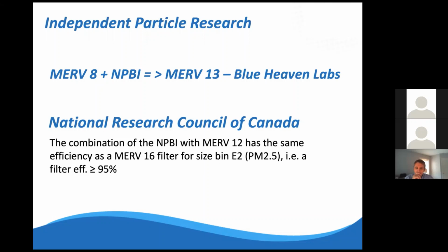So that actually was counterintuitive for me. When I put the HEPA filter in, I thought we were going to see a much better clean air delivery rate, but it comes down to the air exchange rate, and that highly impacts the particle removal in the space itself. So just keep that in mind if you're looking to upgrade from a MERV 8 to a MERV 13.